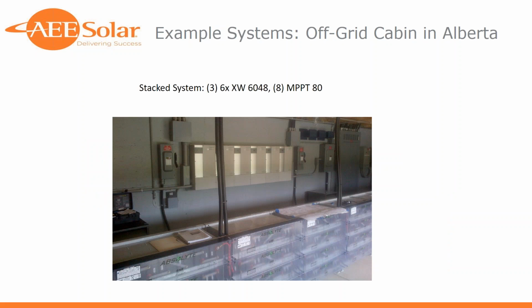This system, same general type of architecture, a little more complicated. So this is a, let me count them up here, 1, 2, 3, 4. This is a 6XW cluster. You see here lots of disconnects. You see here on the right the panel board that they're feeding. And I don't think we're looking at the entire battery bank, but a more high capacity system that's basically off-grid DC coupled. So plenty of examples out there. And I know you guys have seen examples of grid tie DC coupled as well.